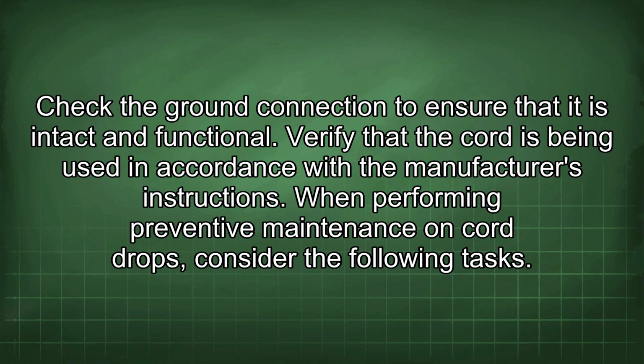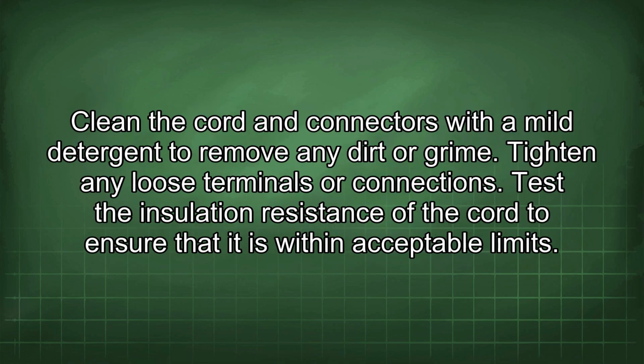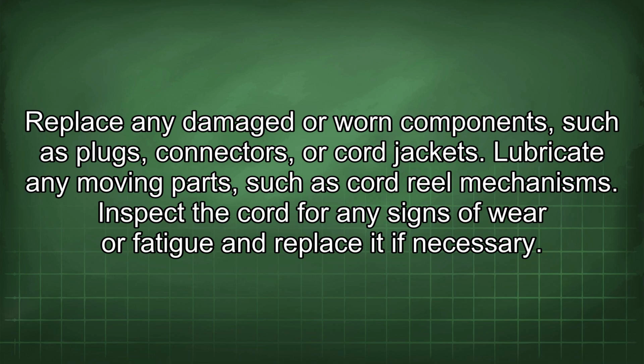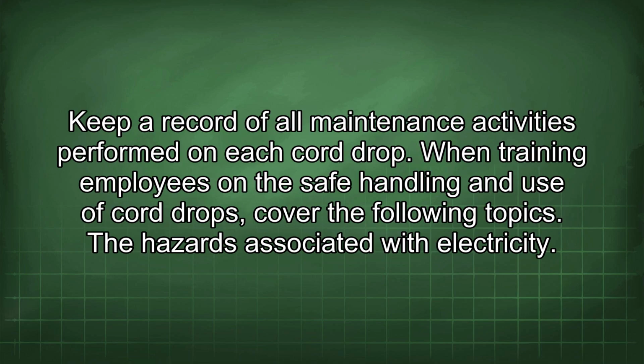When performing preventive maintenance on cord drops, consider the following tasks. Clean the cord and connectors with a mild detergent to remove any dirt or grime. Tighten any loose terminals or connections. Test the insulation resistance of the cord to ensure that it is within acceptable limits. Replace any damaged or worn components such as plugs, connectors, or cord jackets. Lubricate any moving parts such as cord reel mechanisms. Inspect the cord for any signs of wear or fatigue and replace it if necessary. Keep a record of all maintenance activities performed on each cord drop.